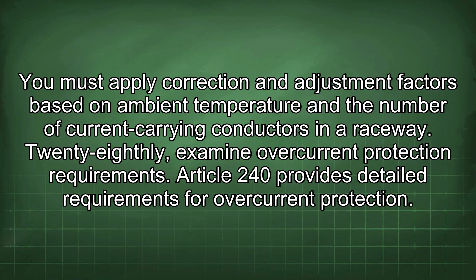28th, examine overcurrent protection requirements. Article 240 provides detailed requirements for overcurrent protection. You need to understand how to properly size circuit breakers and fuses based on the ampacity of the conductors they protect. This involves considering factors such as motor starting currents and appliance loads.